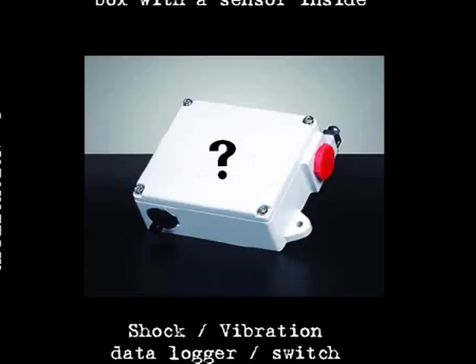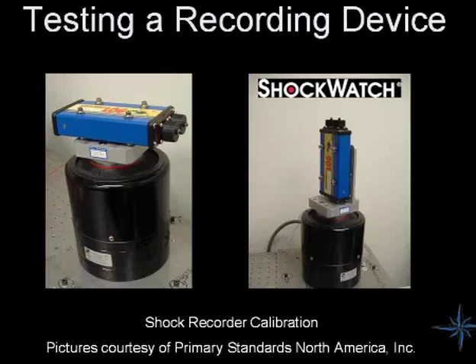And a lot of times those boxes are too heavy for our calibration shaker, for the air bearing shaker. And a lot of times also the customer is not looking for a full-blown calibration workstation. They don't want to calibrate this according to the ISO standards. It's much more either a verification or making sure the system is working.